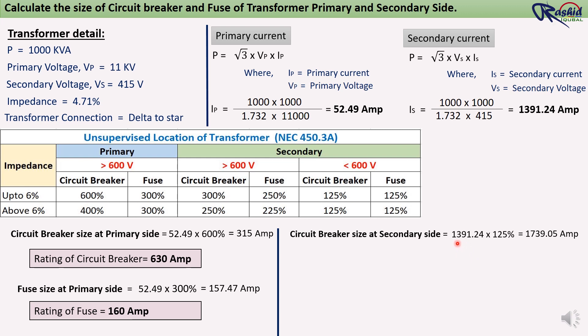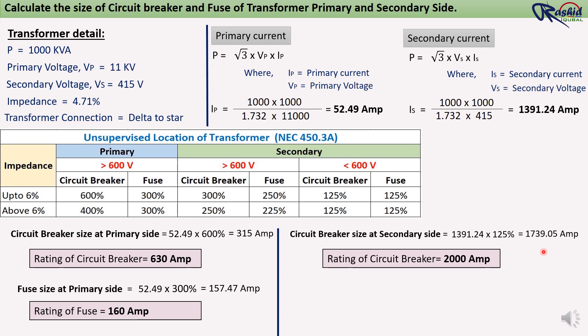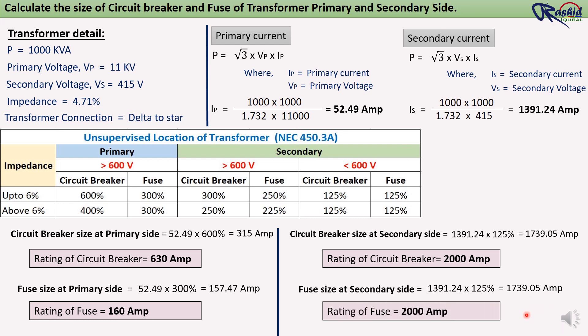After multiplying by the 125% safety factor, we get 1739.05 ampere. Since a 1739 ampere circuit breaker is not available in the market, we use the next bigger available size, which is 2000 ampere. So we will use a 2000 ampere circuit breaker. For the fuse, multiplying 125% by the secondary current also gives 1739 ampere, so we use a 2000 ampere fuse as well.